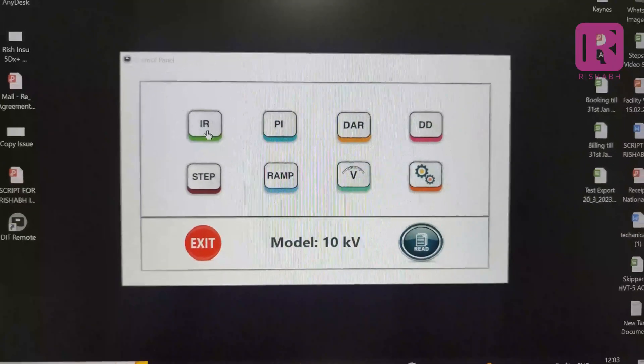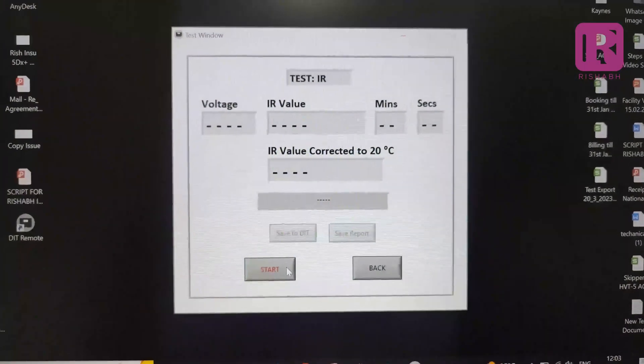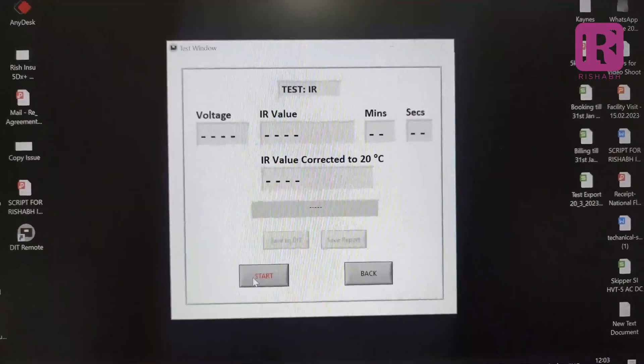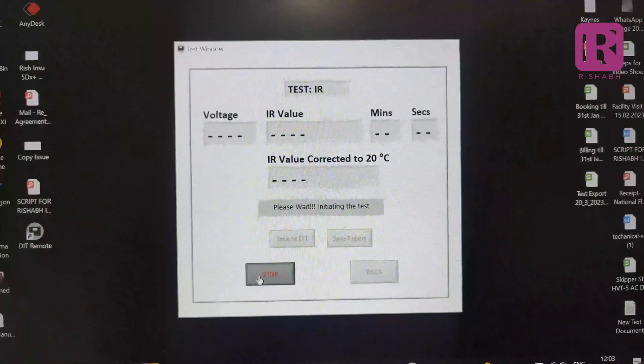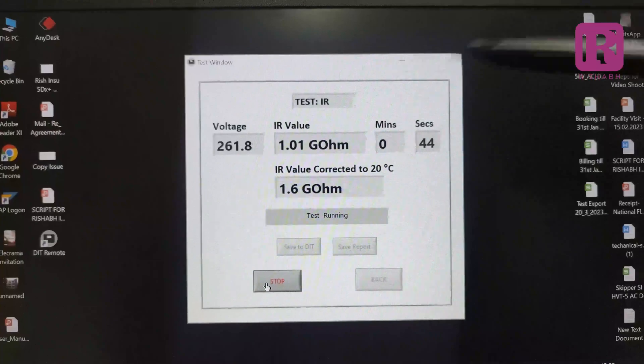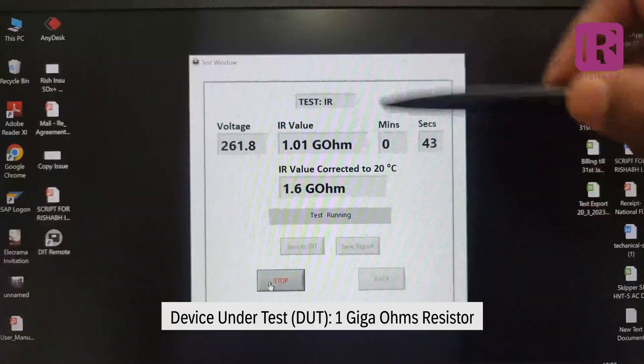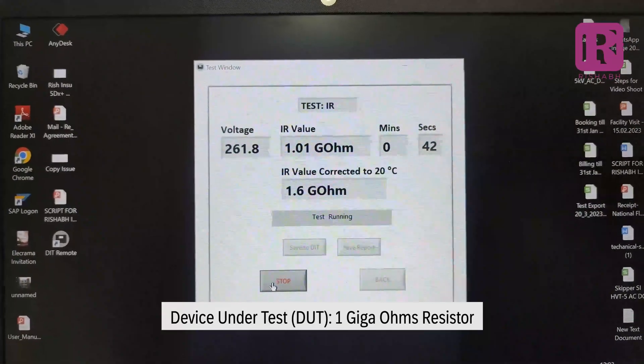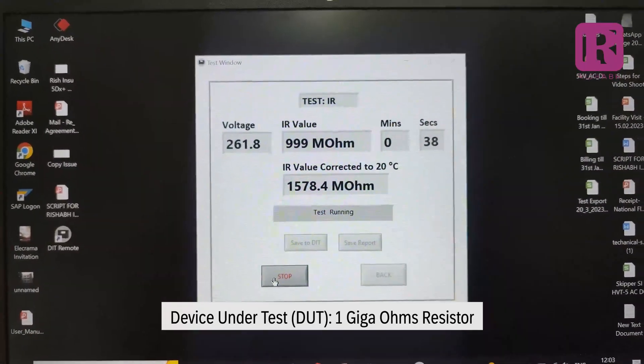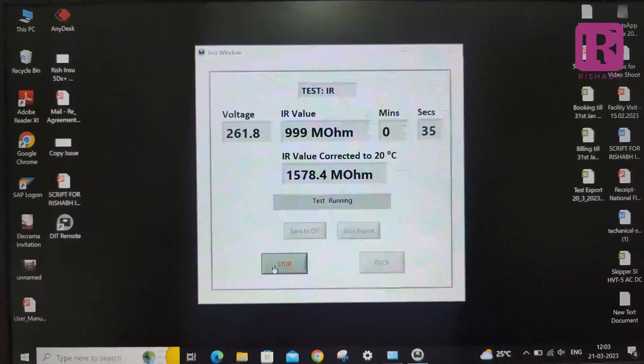Go to the IR measurement and press start button. The test will start in which test voltage, IR value and test time will appear on the application software. Below the IR metered value, you will also see the IR value corrected to 20 degree Celsius.